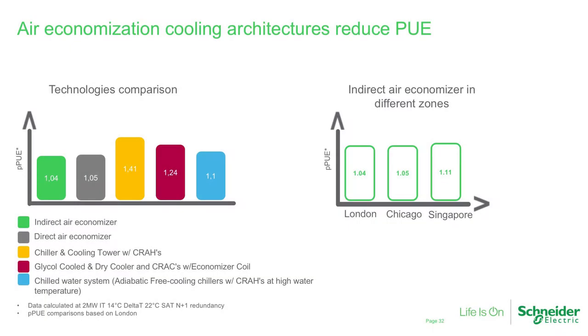This is a comparison of indirect versus direct versus chillers, glycol cooling. No matter how you do it, indirect and air economization gets you a pretty good partial PUE—this says 1.04. And if you take indirect across London, Chicago, Singapore, you get similar numbers. So you get very good efficiency out of air economization, and we're trying to make it as practical as possible for people to implement that technology.